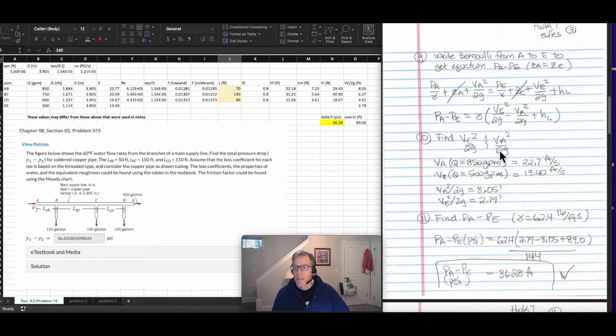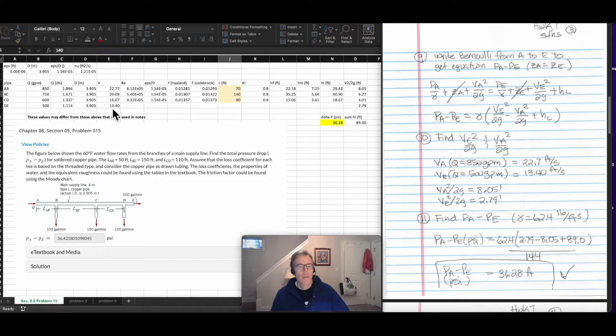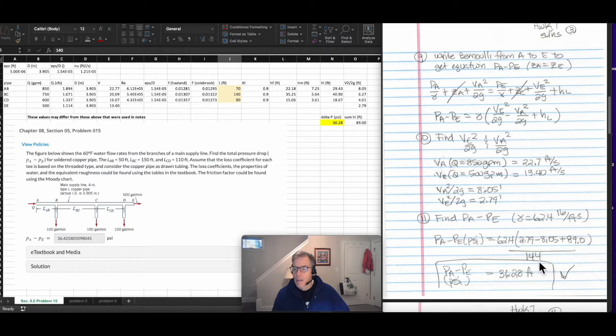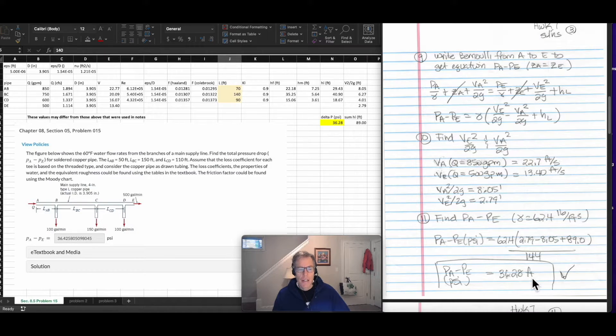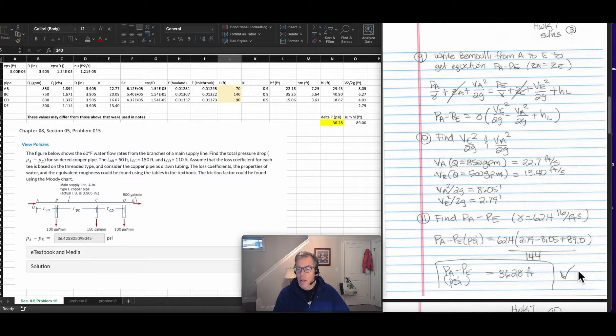I needed to calculate the velocity heads at E and A. The velocity at E is calculated in my spreadsheet, and the velocity head is there as well. I then had everything needed to calculate the difference in pressures: unit weight times the difference in velocity heads plus the head losses, divided by 144 to convert to PSI. I get a value for the pressure difference of 36.28 PSI. For a slightly different set of values I get 36.4 PSI, and when I checked that, I got it correct.